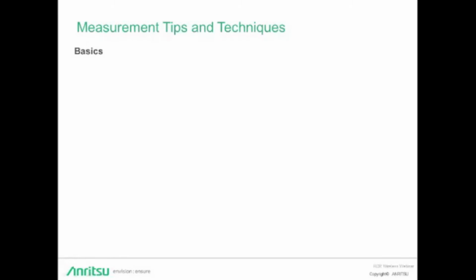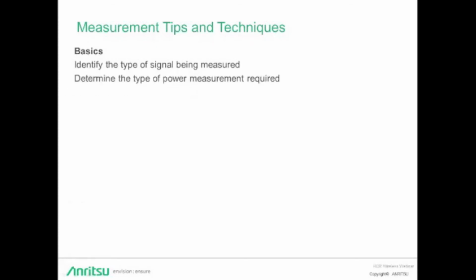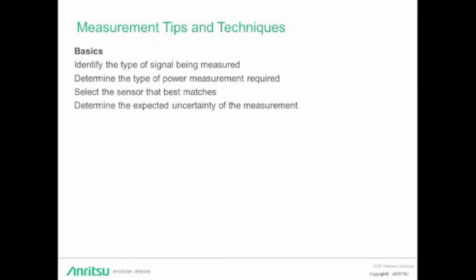Remember, the quality of a sensor is reflected in its measurement accuracy. For power sensors, the achievable measurement accuracy is typically specified under the reference conditions. So consequently, it's very important to become familiar with the manufacturer's specifications and determine what additional error sources exist that can influence measurement. So again, here's some basic tips for identifying your measurement uncertainties. First, identify the type of signal being measured and the type of power measurement required. Select the sensor that best matches those needs. Determine the expected uncertainty of the measurement.